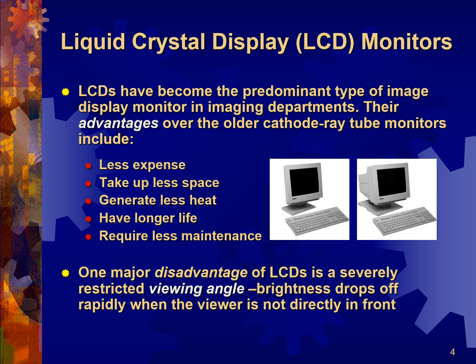Brightness drops off dramatically when the direction of your eyeballs and your line of sight is not perpendicular to the plane of the monitor. Then you're going to experience diminished brightness. And so leaning back in your chair at an oblique angle to the QC station and saying, yeah, that image looks good, that tech has no idea what the actual image looks like.